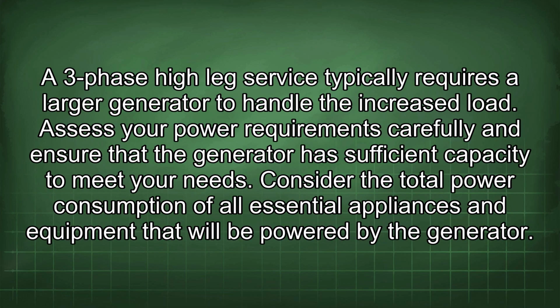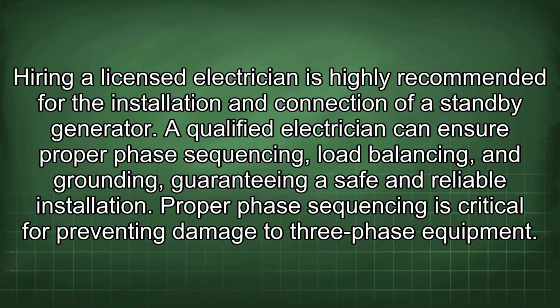A three-phase high-leg service typically requires a larger generator to handle the increased load. Assess your power requirements carefully and ensure that the generator has sufficient capacity to meet your needs. Consider the total power consumption of all essential appliances and equipment that will be powered by the generator. Hiring a licensed electrician is highly recommended for the installation and connection of a standby generator. A qualified electrician can ensure proper phase sequencing, load balancing, and grounding, guaranteeing a safe and reliable installation.